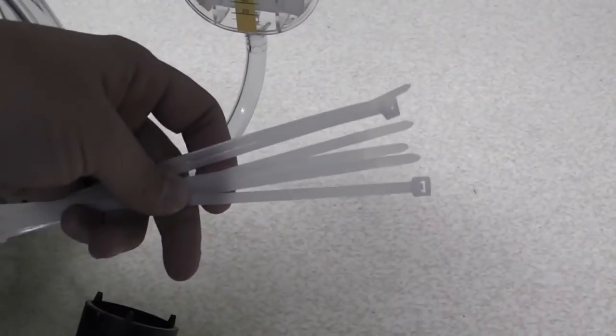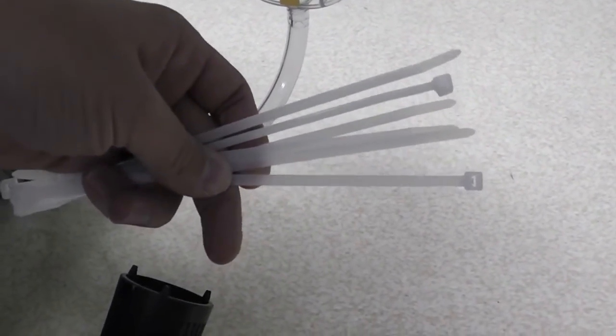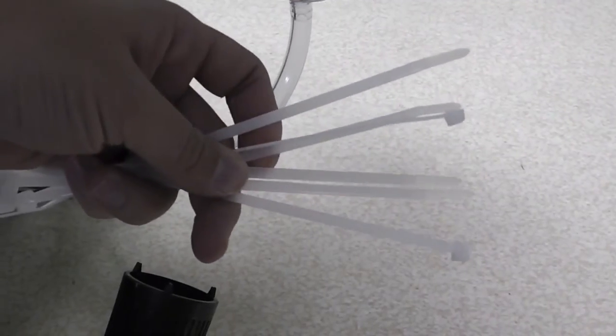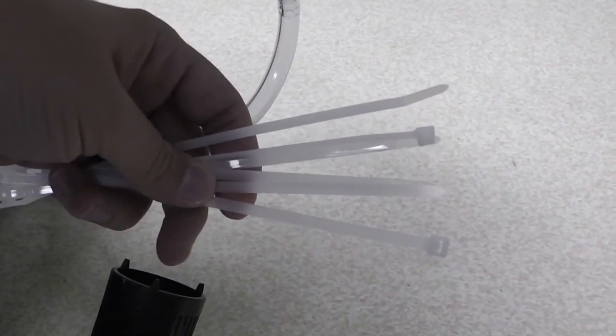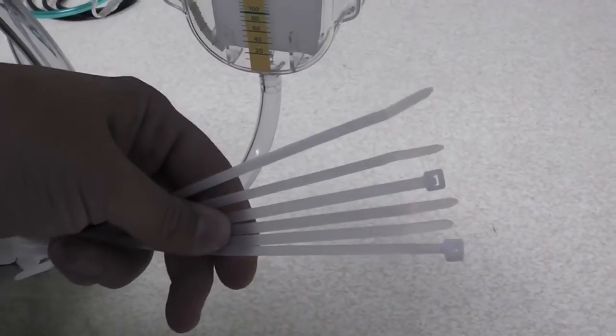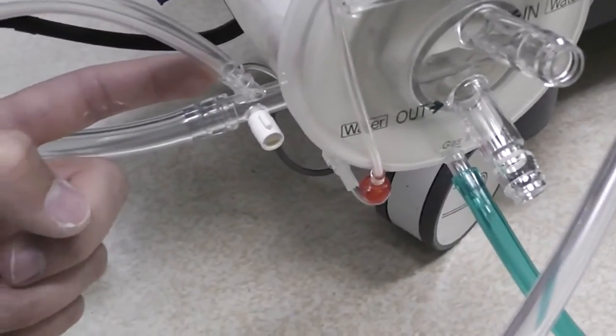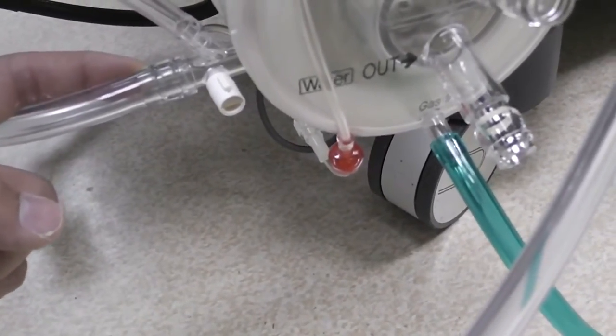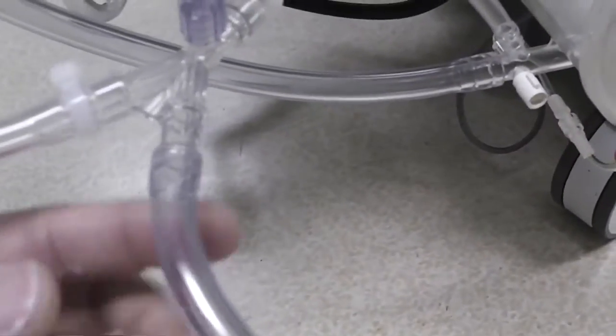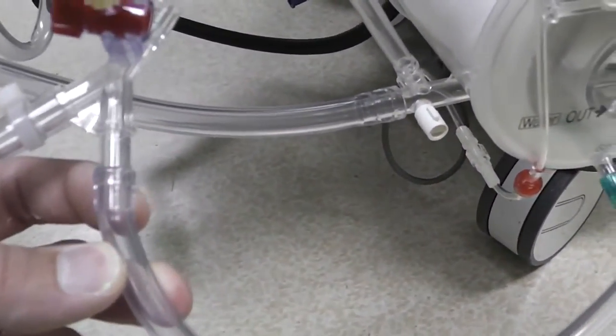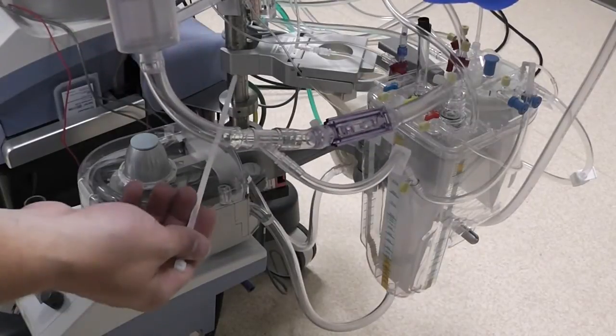So now we need to gun tie a lot of these high pressure connections that we've made. So I grabbed 6 gun ties, and I'll show you where I place those. 5 of them are required, and the 6th one is not really needed, but I find to be helpful. But the required connections are here at the bottom of the reservoir, at the inflow to the oxygenator, at the connection of the stub line, the outflow from the oxygenator of the arterial line, and then this Quest connection for the blood cardioplegia.